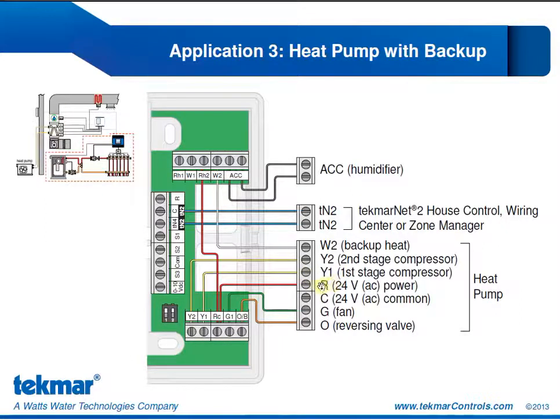Our first and second stages of heat from the heat pump are going to be controlled with the Y1 and the Y2 connections. We also have the power coming in from the heat pump. We're connecting our backup heat, W2, at the heat pump as well. And we have our fan operation and O for the reversing valve.